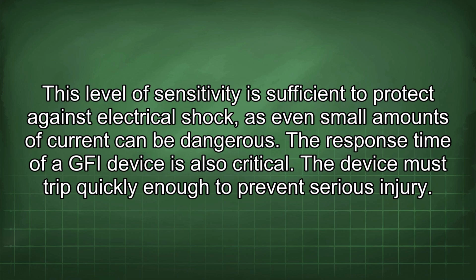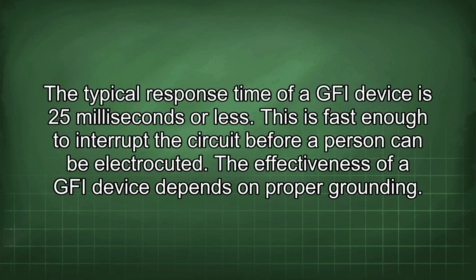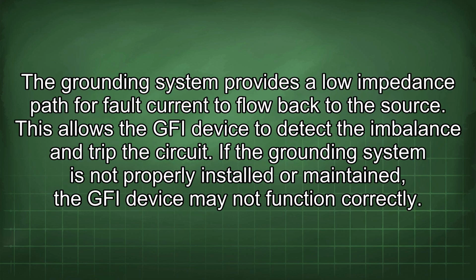The response time of a GFI device is also critical. The device must trip quickly enough to prevent serious injury. The typical response time of a GFI device is 25 milliseconds or less. This is fast enough to interrupt the circuit before a person can be electrocuted. The effectiveness of a GFI device depends on proper grounding. The grounding system provides a low impedance path for fault current to flow back to the source. This allows the GFI device to detect the imbalance and trip the circuit. If the grounding system is not properly installed or maintained, the GFI device may not function correctly.